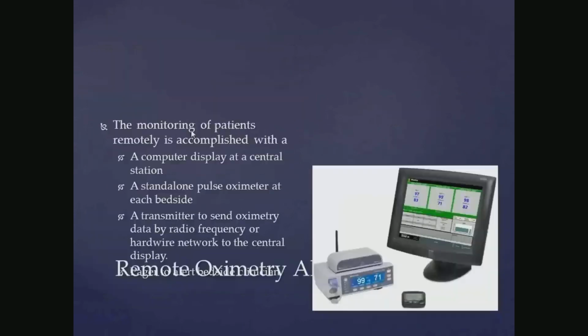So one of the arguments is to do some sort of remote monitoring. There are hospitals that have established, just like you have telemetry monitoring of EKG, telemetry pulse oximetry. This is an example where you can have a radio transmitter going back to a centralized station. The centralized station not only tracks trends, it'll also pick up on the alarm, and they're set up so that when an alarm goes off, it can go to your beeper. Oh, yeah.